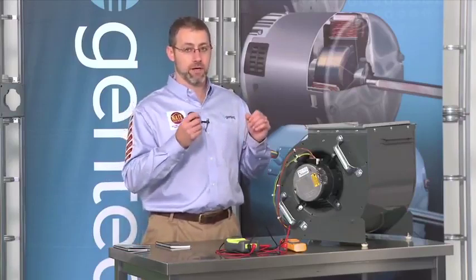However, we could also have problems such as dirty filters, dirty coils, and keep in mind that even though a constant torque motor can help airflow problems, it's not a solution to airflow problems. It's not going to overcompensate for an extremely dirty filter, an extremely dirty evaporator coil, undersized ductwork, or closed registers and grills.